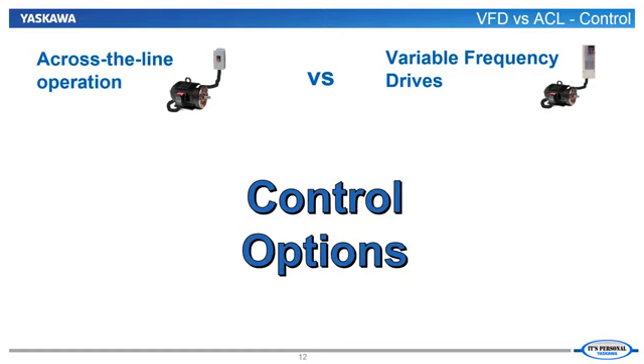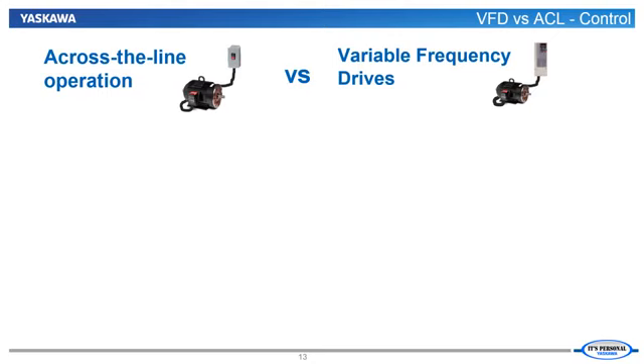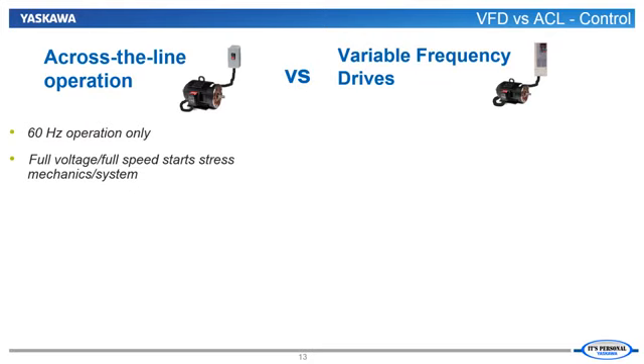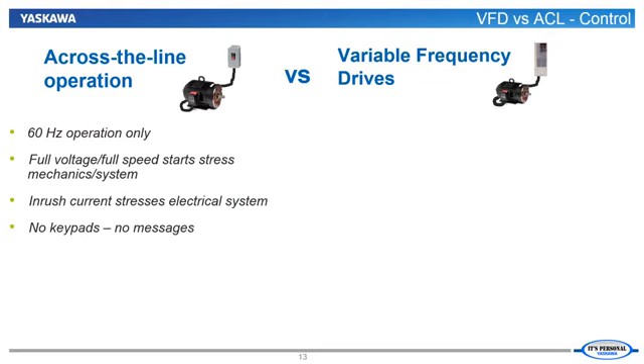Our next face-off between VFD operation for fans and pumps versus across-the-line operation will be over control options. The features considered next will go directly to how easy it is to work with each technology. When it comes to control options and capabilities, it really is a one-sided battle. The across-the-line installation has to run at full speed, starts with full voltage, which is stressful for both the mechanical and the electrical systems. It has no keypad, and it won't talk on any network.